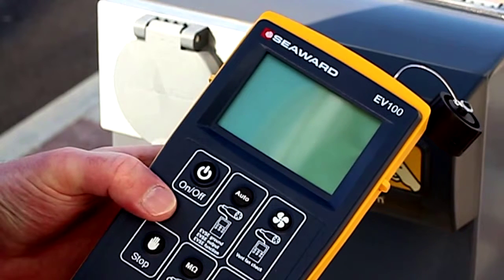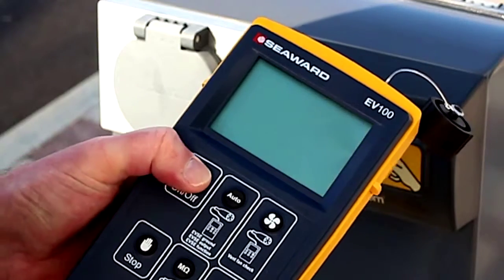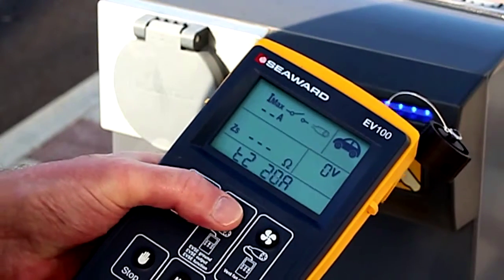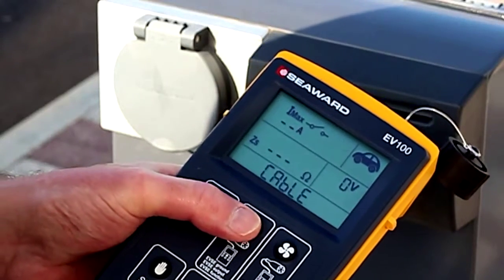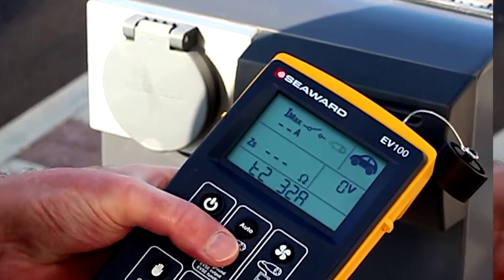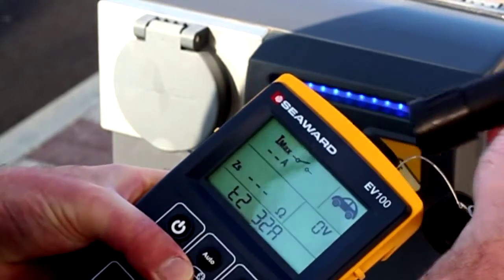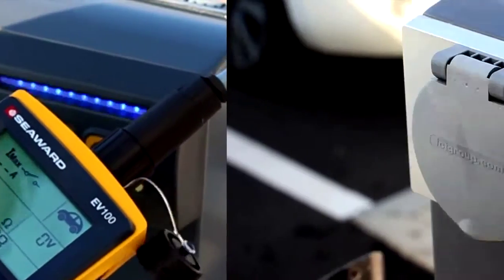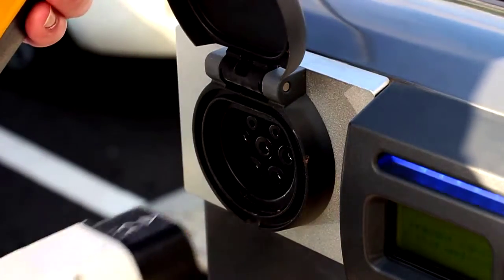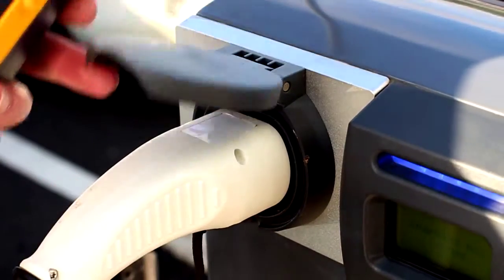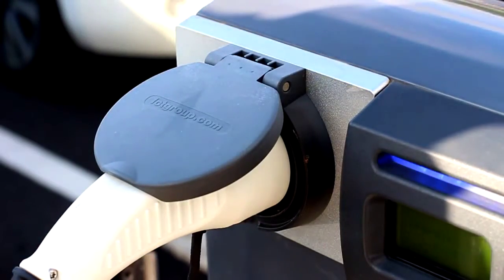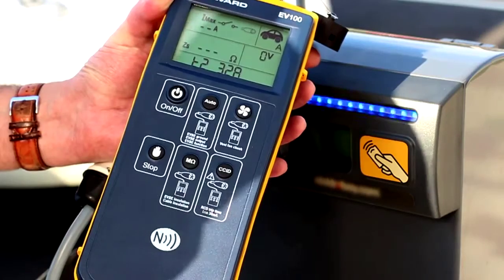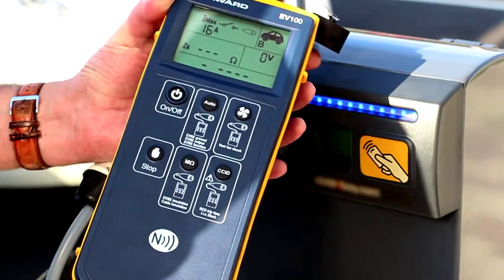To perform the short auto-sequence, press the on-off key to turn on the unit. Using the auto-key, select the type of cable you would like to simulate from the list. Connect the required test adapter to the EV tester. Then connect the EVSE to the EV tester using the test adapter. Press the auto-key. The EV tester will now run through the auto-sequence.